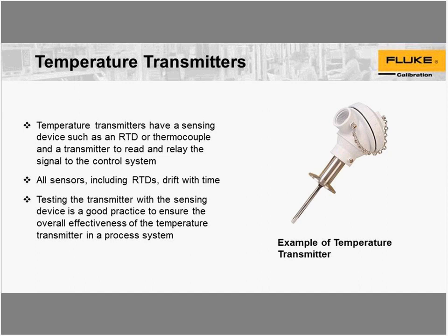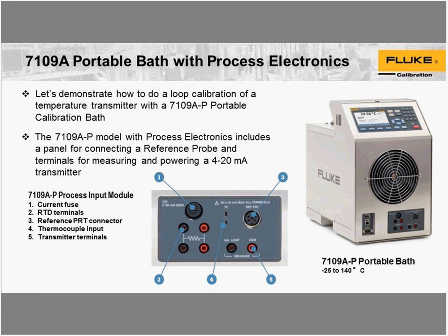Then your measurement system needs to account for the accuracy of the 4 to 20 milliamp measurement capability of the transmitter. So the temperature sensor has its own, possibly its own calibration, like we talked about. And if you calibrate the sensor by itself, then you also calibrate the 4 to 20 milliamp circuit, because it's acting as the readout for the sensor. Calibrate them as a system. So we're going to talk now about just calibrating the transmitter for the temperature itself. So it's calibrated by connecting it to the milliamp loop circuit, as in this picture. And let's see, am I getting ahead of myself here?